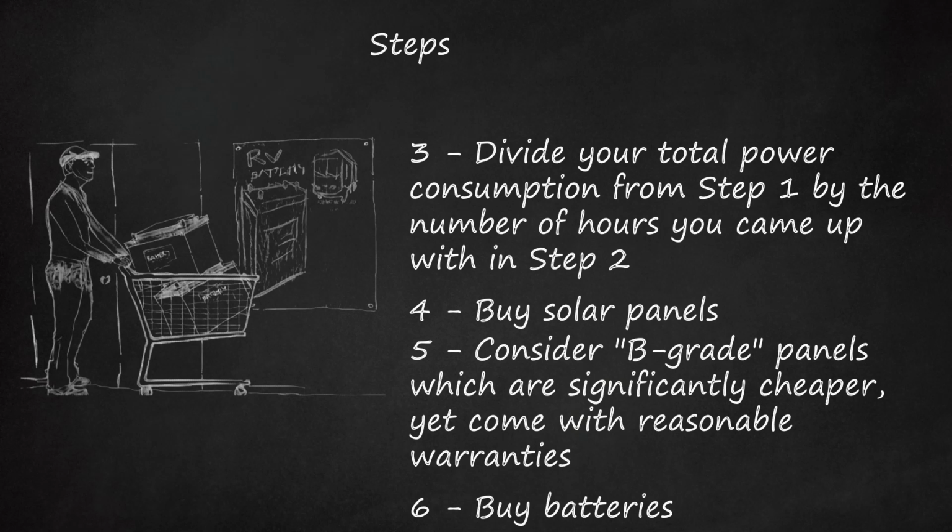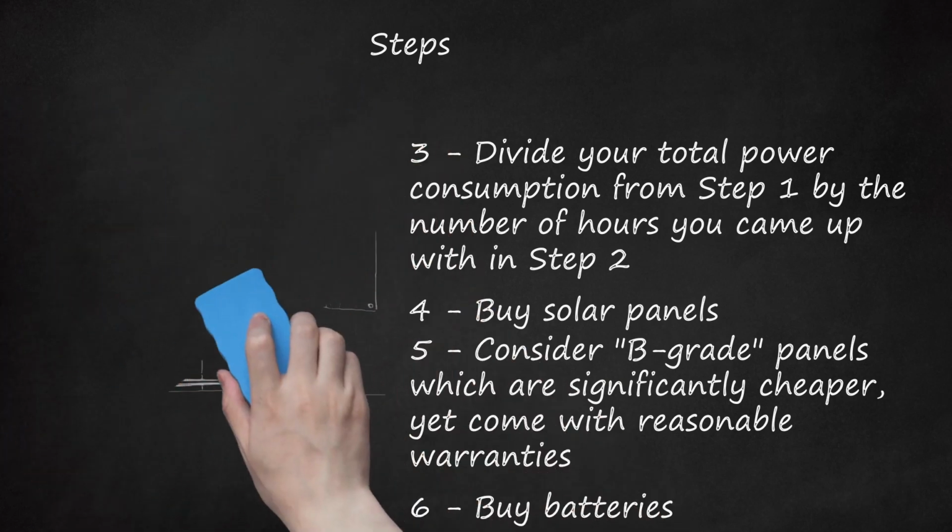batteries cost. Make sure the Ah ratings of all batteries added together is higher than the capacity you calculated in the previous step. If using multiple batteries, make sure to get multiples of the same battery, and to get them all new, or reconditioned, at the same time. Mixing different capacity, model, or age batteries can shorten all of their lifespans.